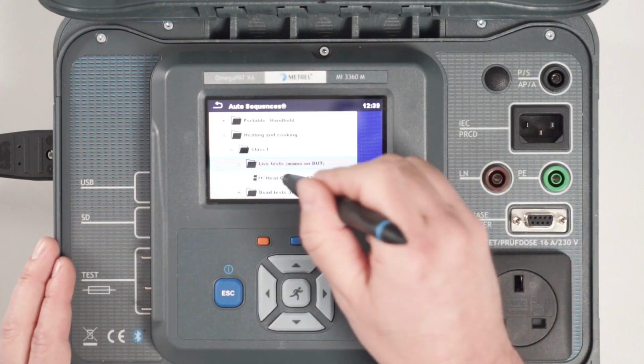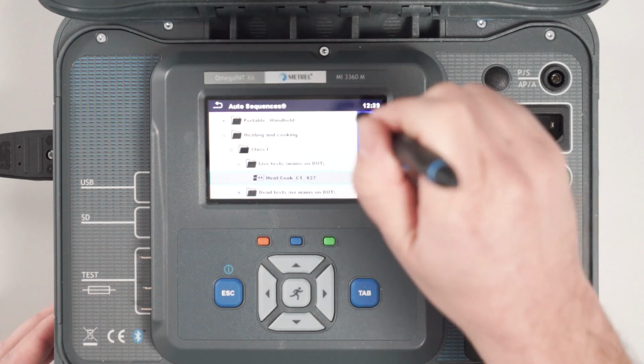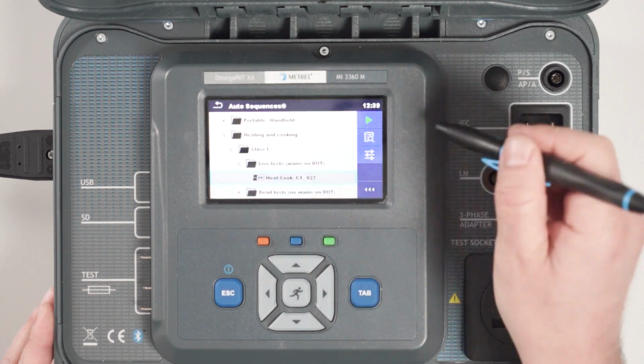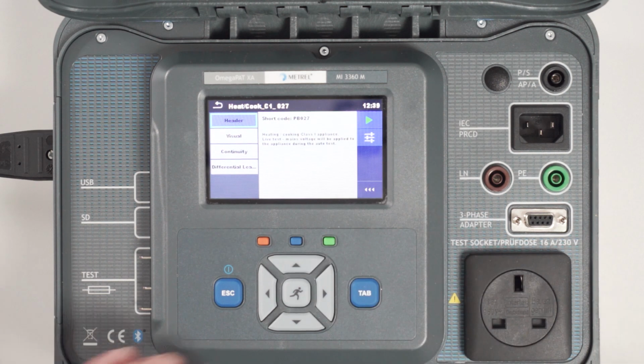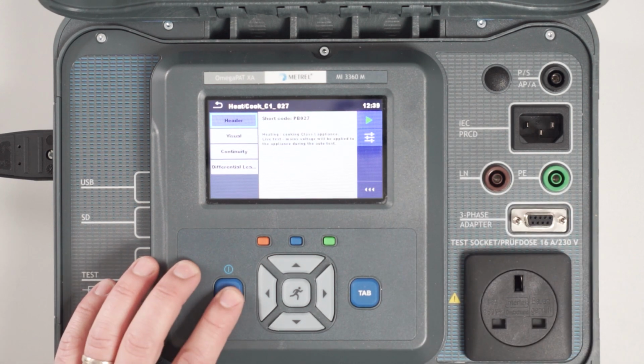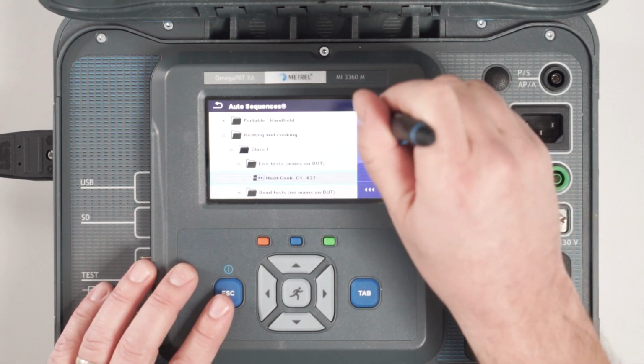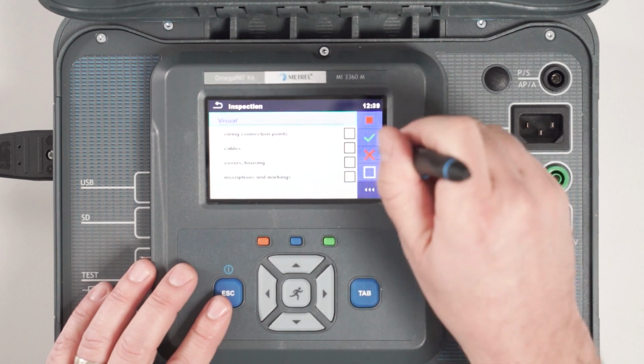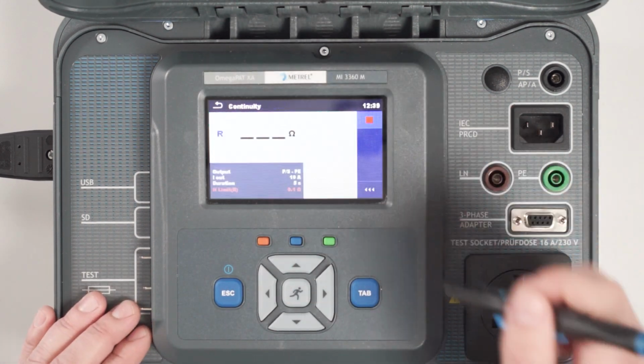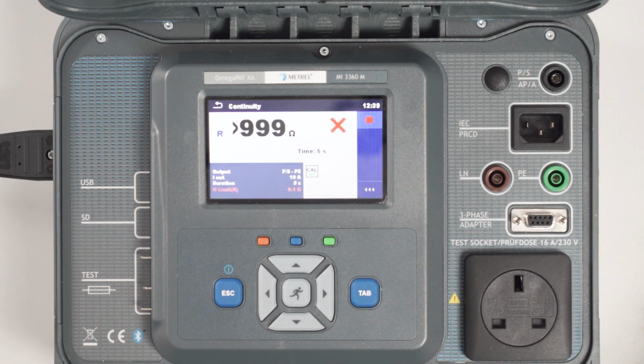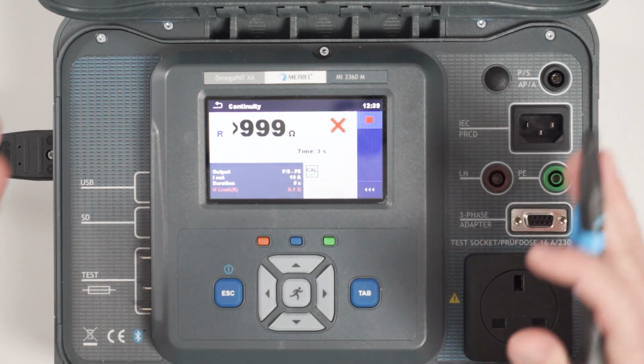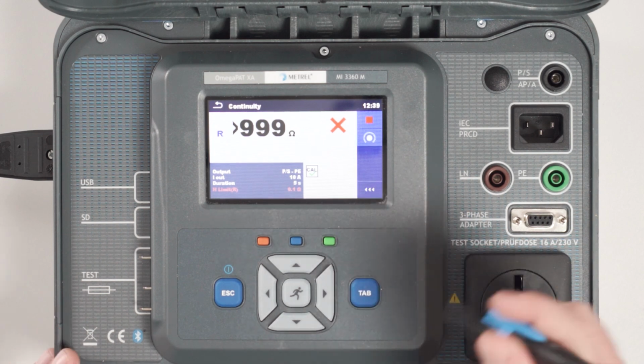We simply select one of the auto sequences and we can run the test, or we can even adjust the test limits and parameters prior to starting the auto sequence itself. So this is one option, so we can basically start here. The auto test will automatically start. We confirm our visual inspection and proceed to other tests. Of course, now we don't have anything connected here, so the test will fail.